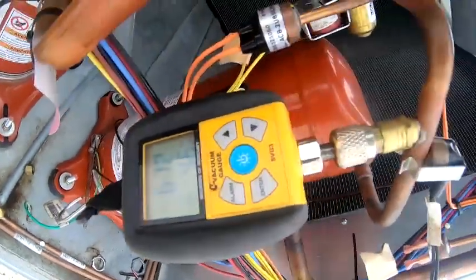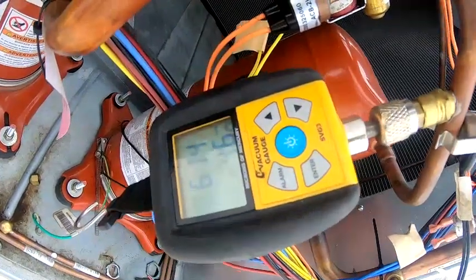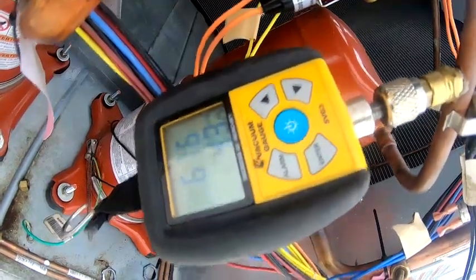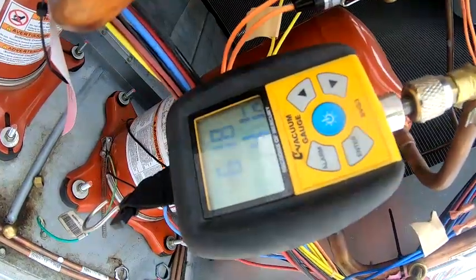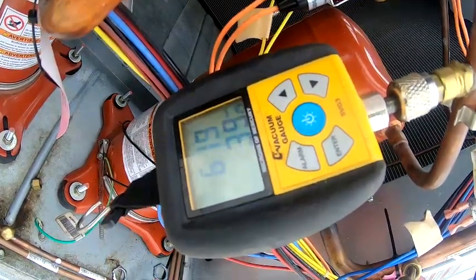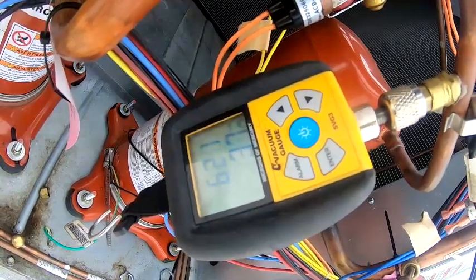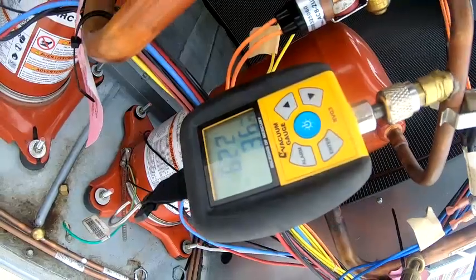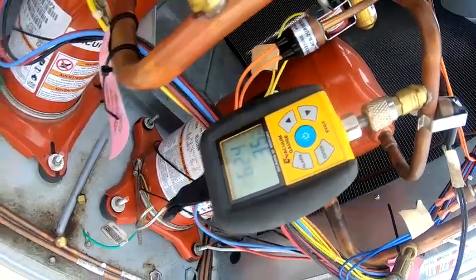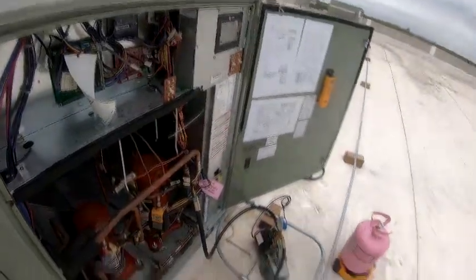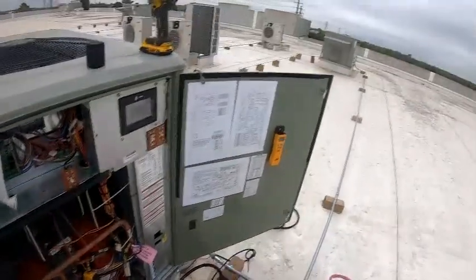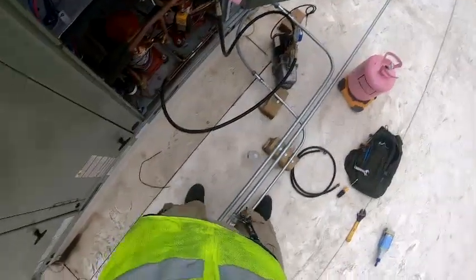Try to turn the camera upside down. Let me see it. Just isolate the micron gauge for 5 minutes. Make sure it doesn't go above 1,000 in 5 minutes. Like I said, if it goes above 1,000 and those numbers go up real fast, you've got a leak in the system somewhere. If you go above 1,000 and it goes up real slow, you probably have moisture in there. That's kind of how you can tell what's going on.